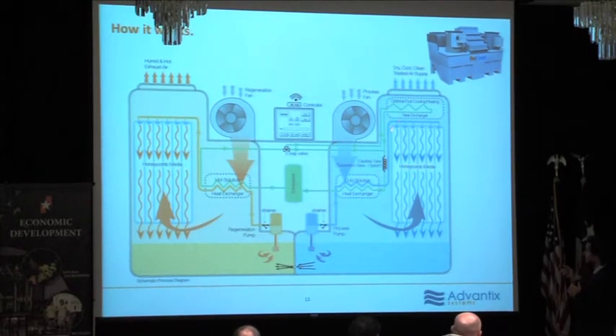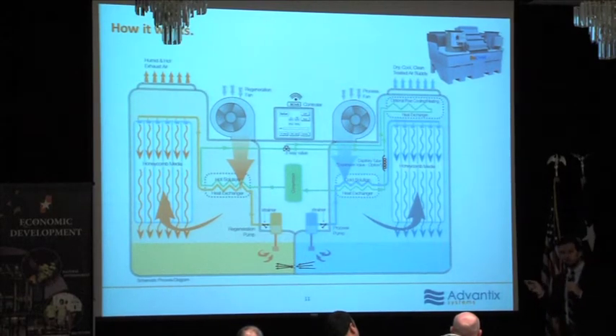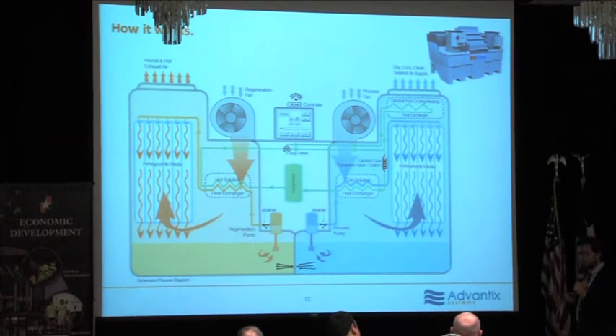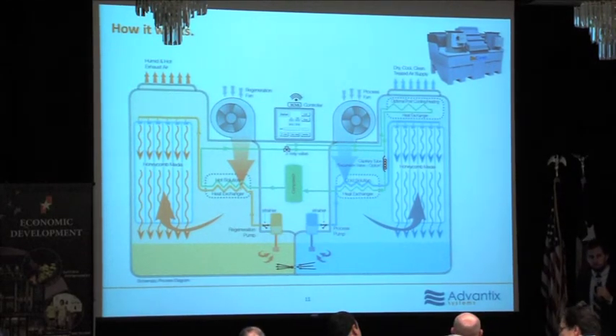Well, I've got a biocidal solution constantly washing over that media. There's no mold growth whatsoever. There's no UV because it's inside. That honeycomb media actually will usually outlive the mechanical components in that system, even though it's only a corrugated cellulose. The lifetime is determined primarily by the binder in that cellulose. So we have to buy high quality corrugated cellulose with good binder.